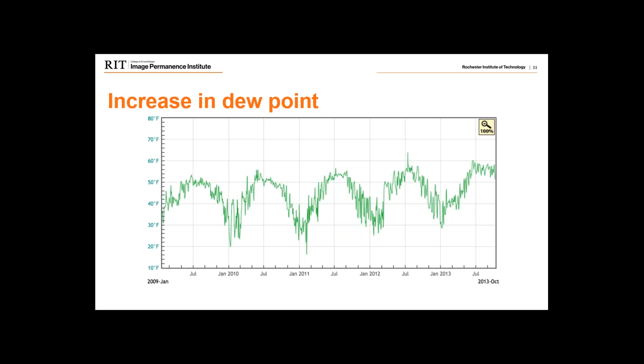and therefore the long-term preservation of collections. Usually when we see this gradual increase in dew point over a period of years, this tends to indicate that if you have a mechanical system present, there's a gradual failure of the cooling coil. And so you may want to look at that component in particular and see if either preventive maintenance needs to be performed or possibly even replacement.